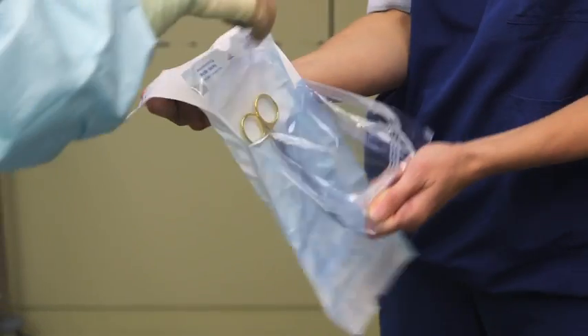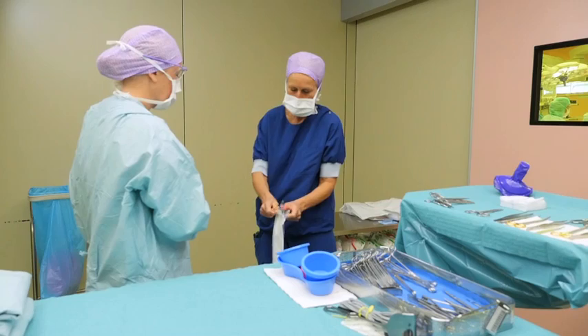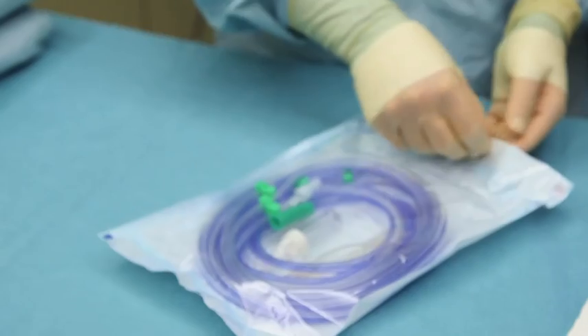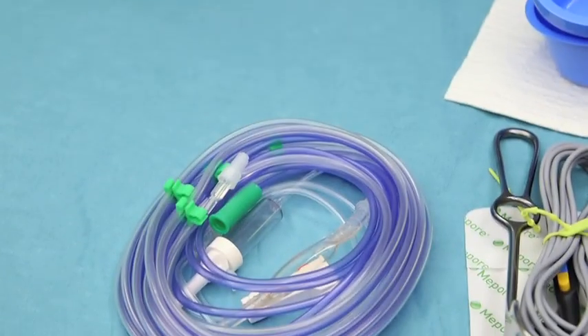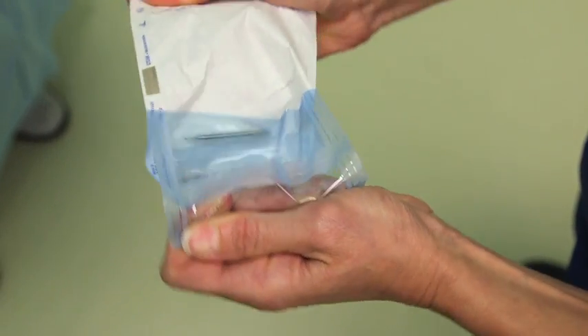The seals of the packs should be peeled slowly and evenly, starting at the specified position depending on the design of the sterile barrier system. This is usually at the chevron end or may be indicated with arrows. For large packs, the best approach is often to start peeling first on both edges so that the last peeling is the middle of the seal. You should respect the direction of peel indicated by a peel symbol. Minimize the creation of fibers and particles without tearing or delamination. Bursting or tearing the barrier system will result in a high risk of contamination. Peel the flap completely and fold it backwards. Maintain the position of the product to avoid contact with unsterile areas of the barrier system, including the seal area.